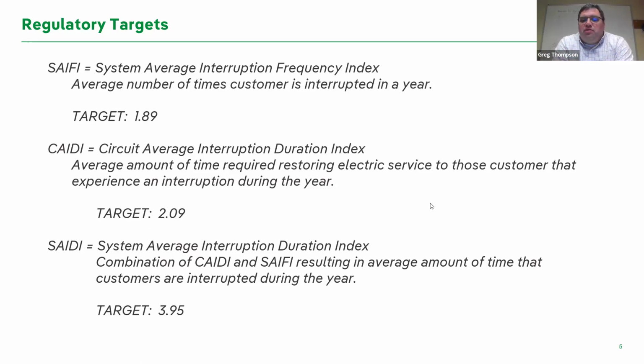SAIFI is basically how many times a customer averages an outage. For example, 1.89, we rounded up - basically each customer's average target is 2 outages per year. Now not everybody has 2 - some have 0, some have more, but that's the average set by the PUC, and our goal is to be less than that 1.89. We just did our reliability targets - we haven't finalized them for 2023, but we're somewhere around the 1.81 metric target. So we're doing okay with that. We still want to get that down, and the goal is every year to push that down some.